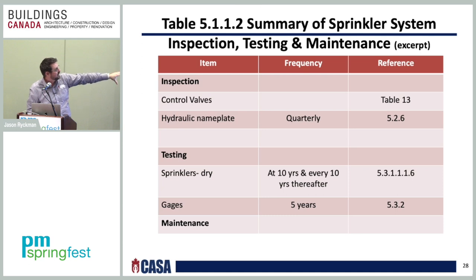So for instance, if you have dry sprinklers, you have to make sure that at 10 years and every 10 years thereafter, they have to be tested at the ULC lab, so Underwriters Laboratories of Canada. You have to ship those sprinklers, a sample amount, to the ULC, which the reference would be 5.3.1.1.1.6.